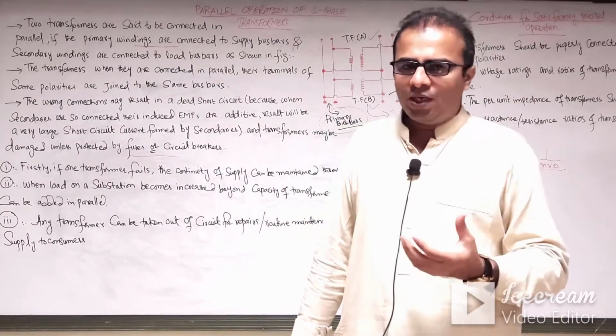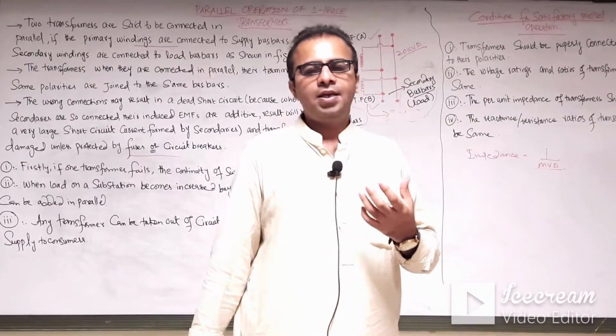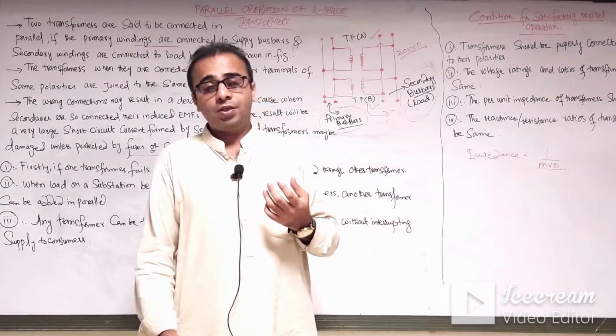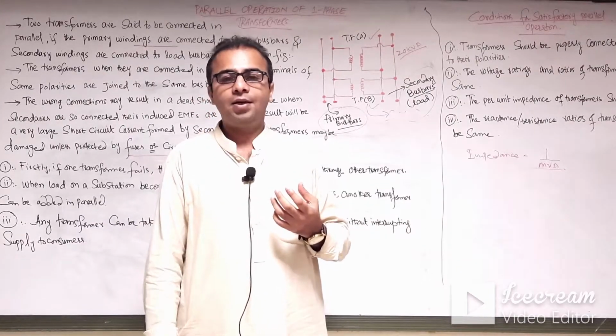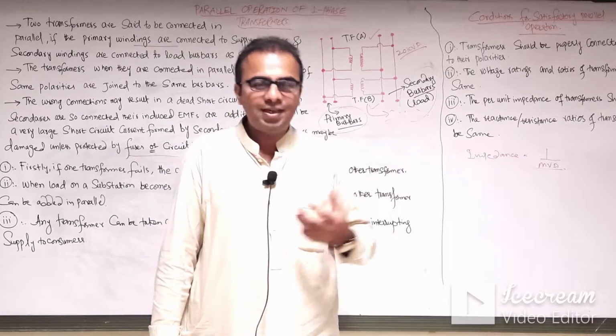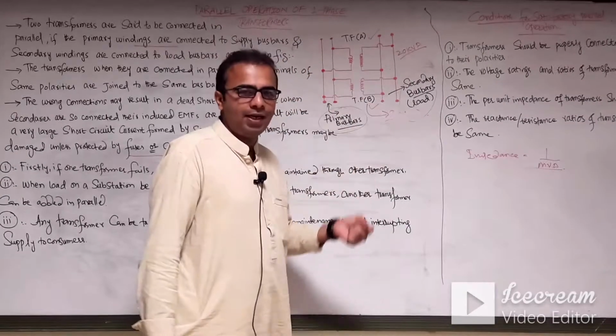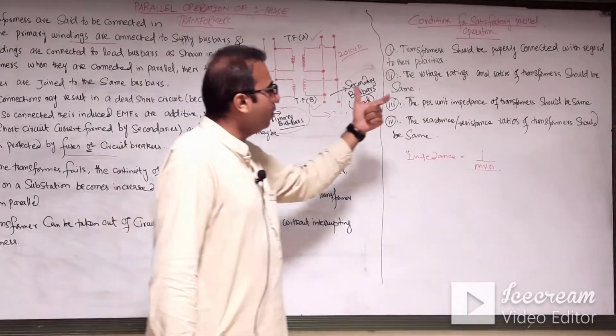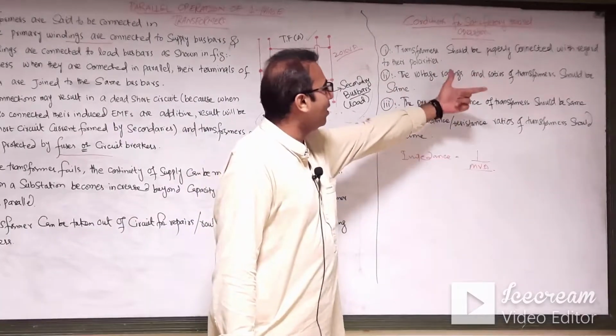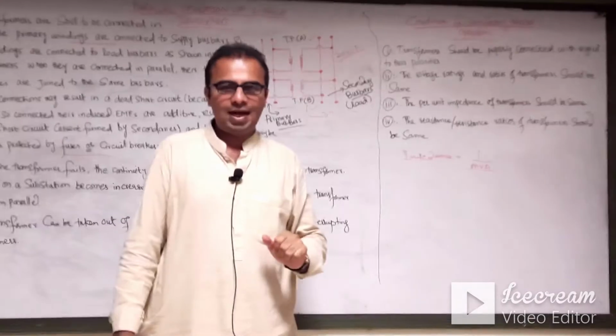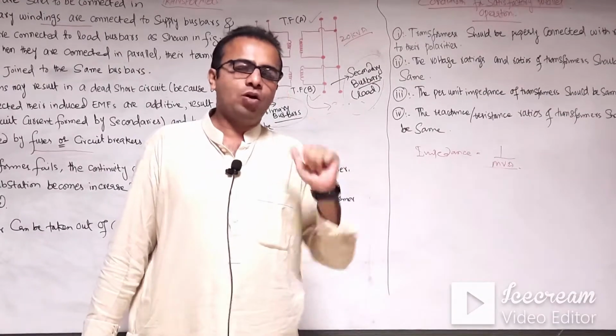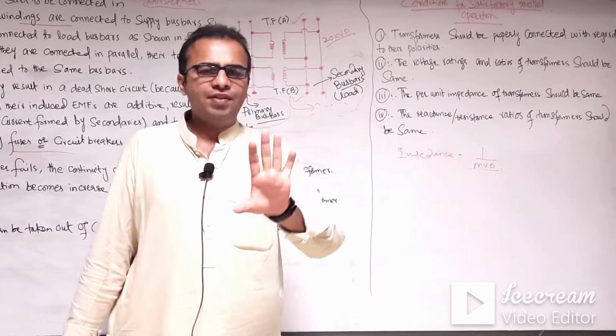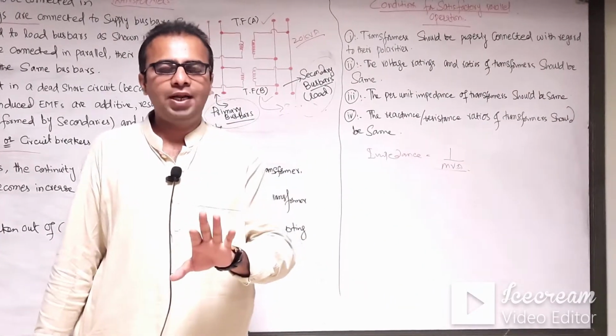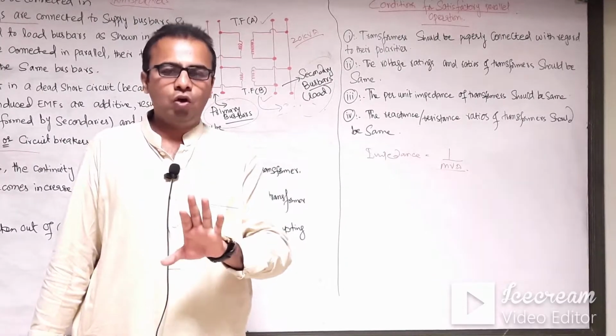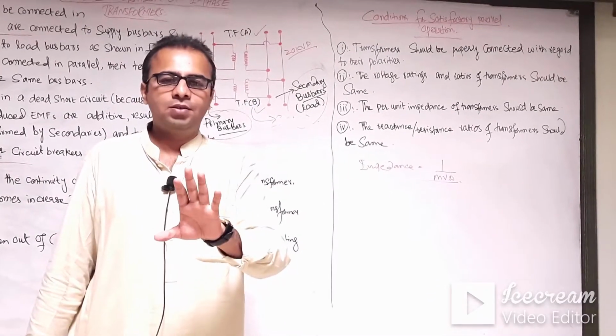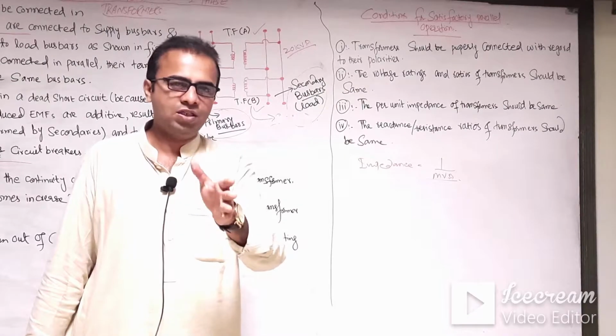Now, what are the essential conditions for the satisfactory parallel operation of transformers when they are connected in parallel? Let's discuss. Number one is that the transformers should be properly connected with regard to their polarities. I have already described that both transformers should have the same polarity. If they have the same polarity, there will be no harmful effect on the transformers.